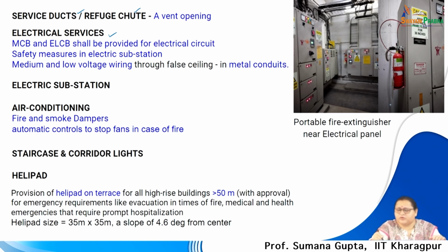So, you see, portable fire extinguishers near electrical panels are supported, and as I told you, electrical fire never works with water; it works with compressed carbon dioxide gas, which replaces the oxygen and puts the fire off. All electrical points should be supported with MCBs. Safety measures are needed in electrical substations, because large buildings or high rise building complexes may also have a substation, and appropriate safety measures are to be kept there, considering these fires can be electrical fires.